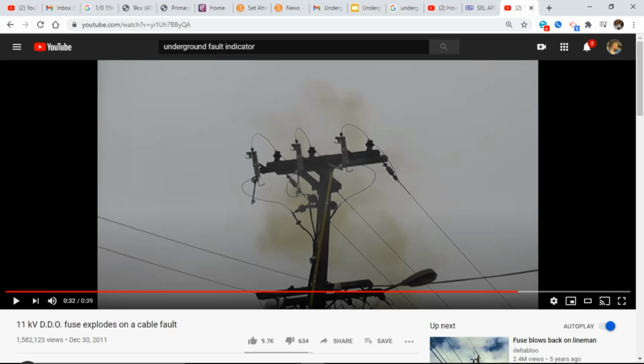They did it on a connection inside an enclosure. All you need to do is replace those connectors that were at the end of the sticks with hooks. Isolate the underground going to the first transformer. That's where my mouse is going. And take one stick here, high pot, and one stick here, high pot, and you can high pot the first span. So I want to make you guys aware of that. They were doing it from a point inside an enclosure. You can high pot the first span.